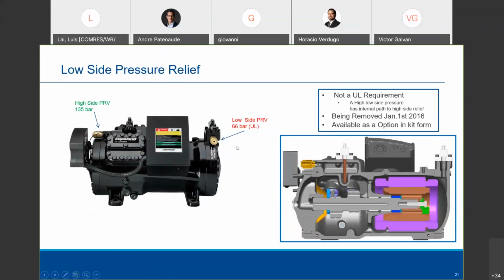I mentioned earlier that initially we had a 66 bar pressure relief valve on the low side. It's no longer, if the customer wants a low side pressure relief valve, we have a 90 bar valve available now, but it comes shipped to us without a pressure relief. That hole is capped from the factory for a while now, almost 4 years.